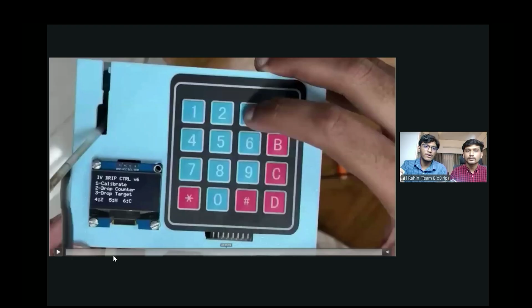Thank you, guys. You mentioned a 40-second convergence time onto your target drip rate. How does 40 seconds compare to competitors, and are there any risks associated with that amount of time? We haven't yet compared it with the results of our competitors. However, we think there is no problem, because whenever we adjust the flow rate, we always start from a precise closed position, so that initially the pipe is fully pressed and no overflow occurs. It takes a time of adjustment, as you can see, 20, 30, 40 seconds, and then eventually goes to the target rate. The main problem that we need to tackle is over-infusion, so that is easily prevented.